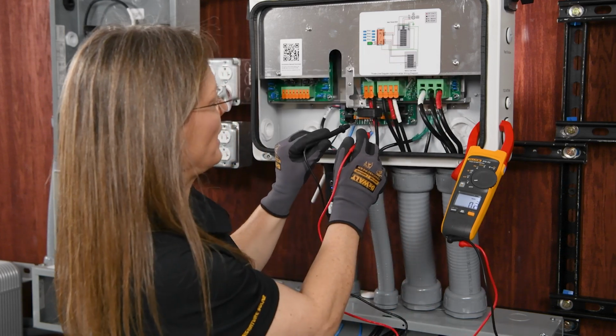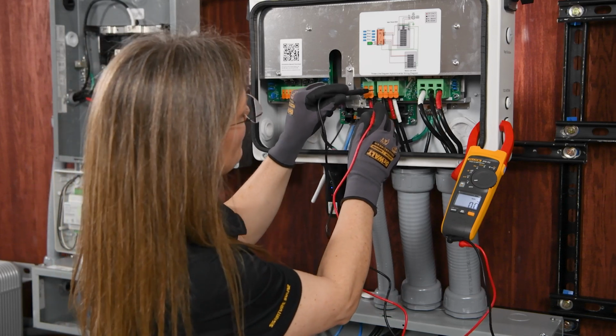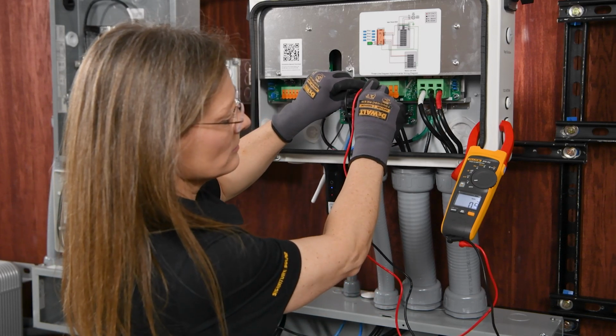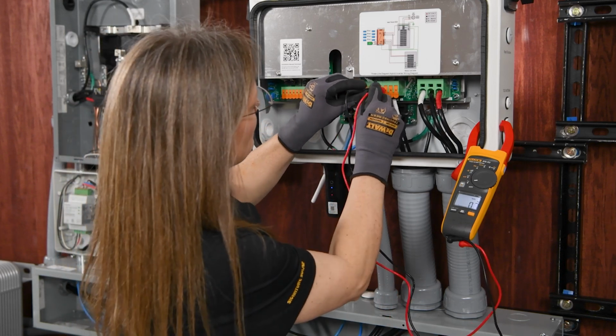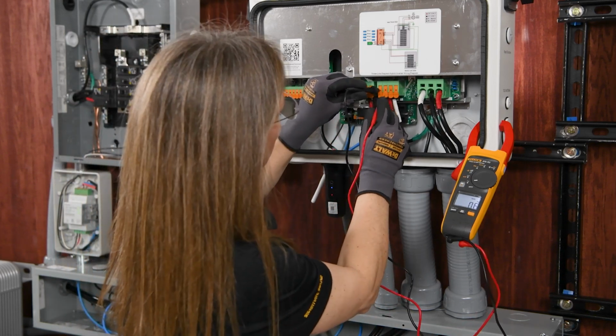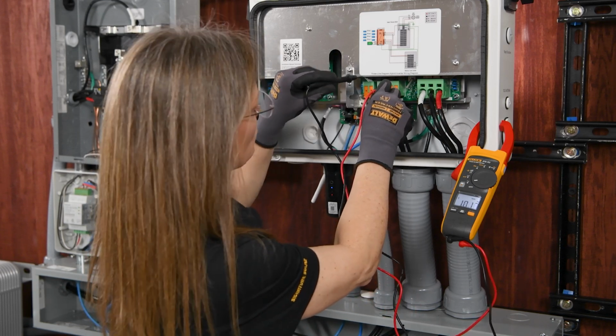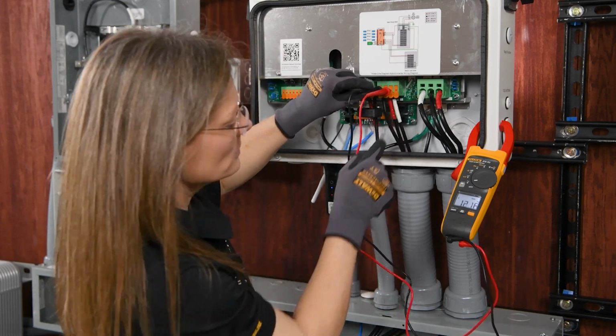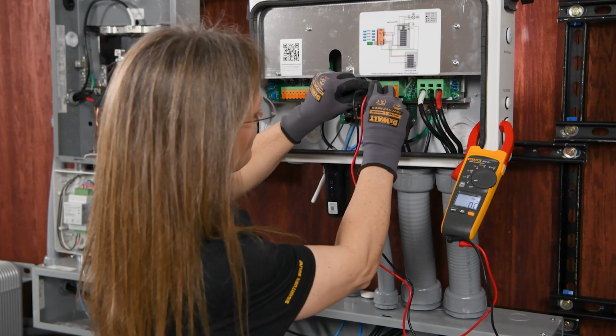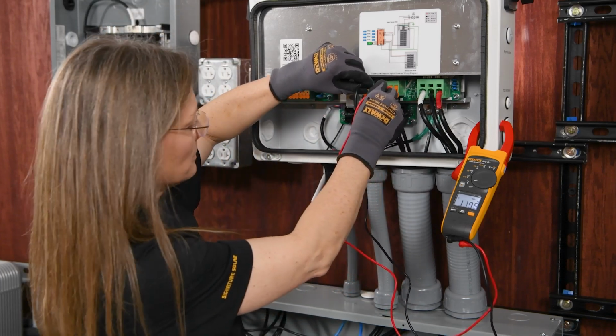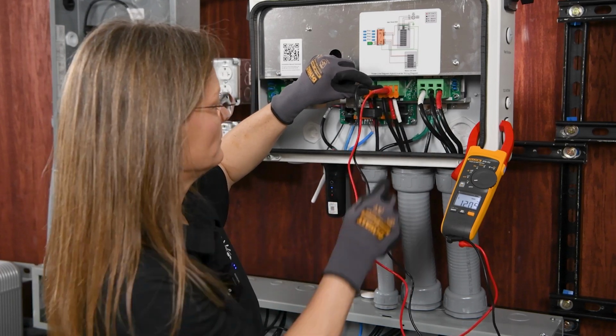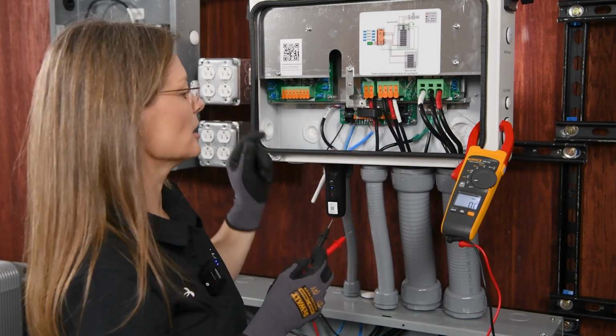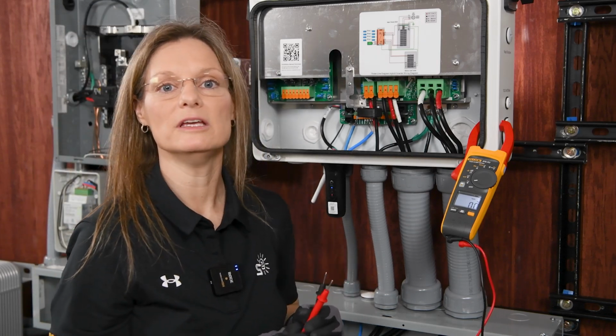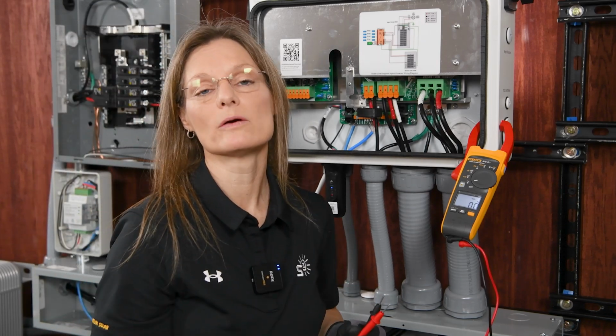We'll also check our backup power. Again, we'll check from line 1 to line 2 here. Make sure we're reading 240, which we are. Then from line 1 to neutral, we get 120, and from line 2 to neutral, we should also be reading 120 there as well. At this point, if you had PV coming in, you could also check your PV voltages coming in. If you were not reading any PV voltage, you would want to make sure that if you had a built-in rapid shutdown button, that is not pushed in.